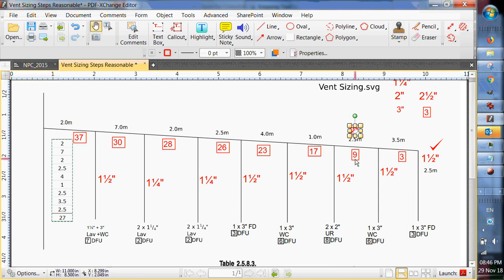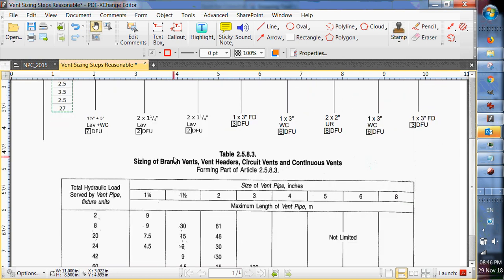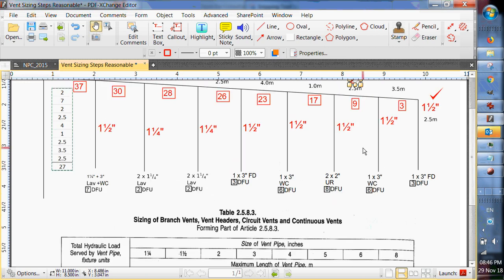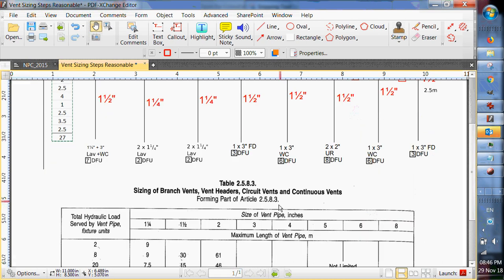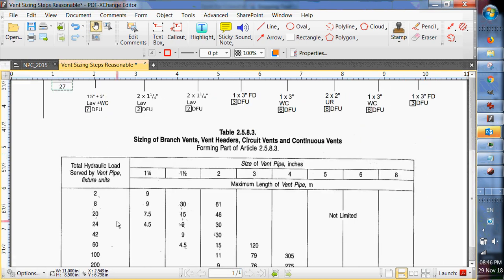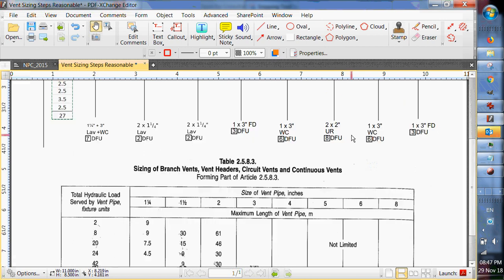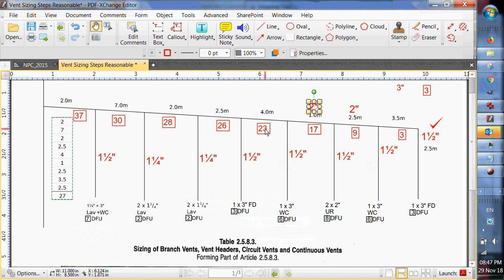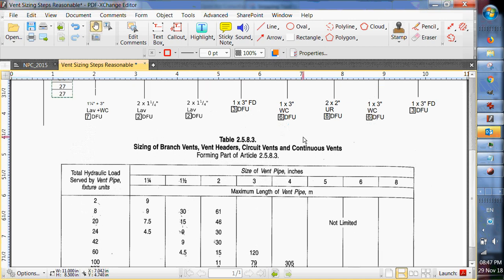Notice I'm putting the numbers here on the pipes and not at the fixtures. If I put it at the fixtures, you can't tell whether I'm talking about this pipe or this pipe. So 17 fixture units. We're still talking two inch. Actually, how many fixture units does that? 20 will do up to 46 meters. So until we get up to 20 fixture units. Oh, here we are here. 23 fixture units. Very next one. So 23 fixture units would take us to this one. We can do that with two inch.